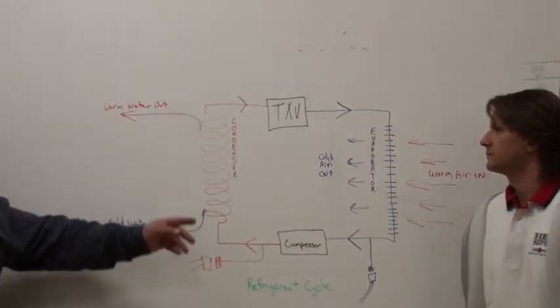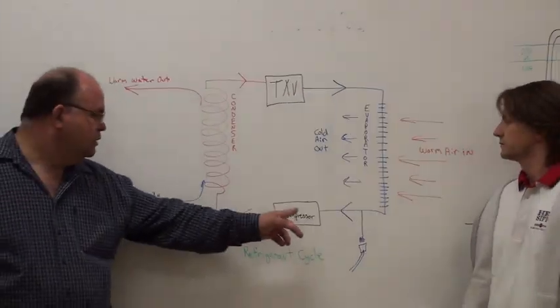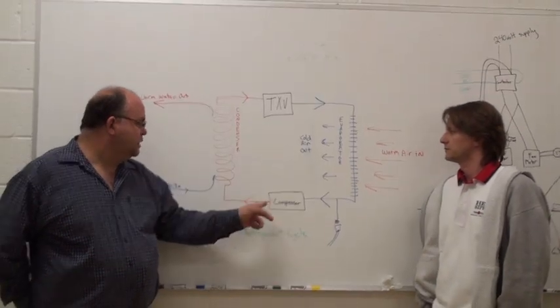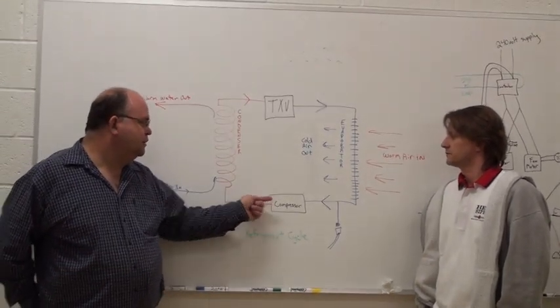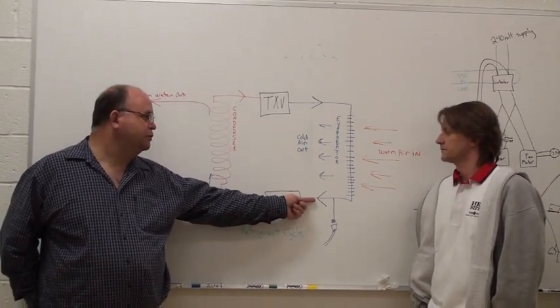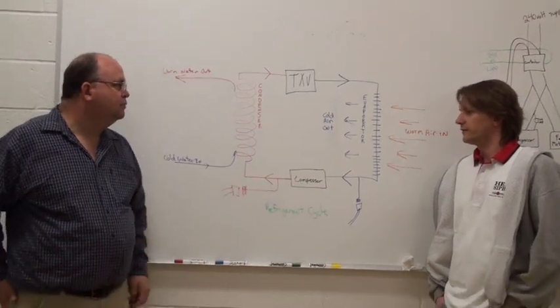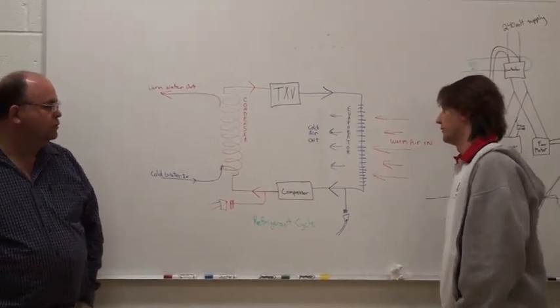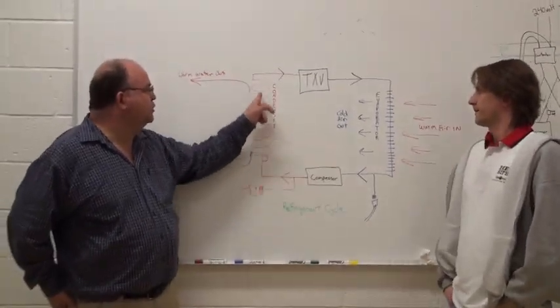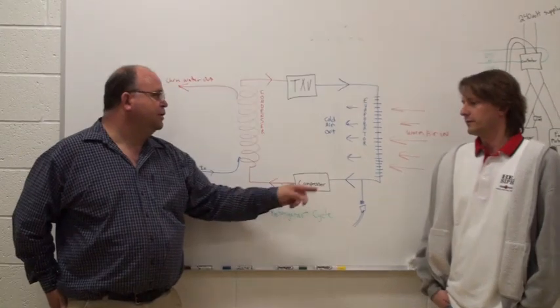You shut it, turned it off, and waited 10 minutes. Does it always flow in this direction? Is there a check valve here on the compressor that doesn't allow the refrigerant to go this way? Well, it's a single-phase motor and it won't go the other way. It has a pressure here that has to work its way around this way to equalize the pressure.